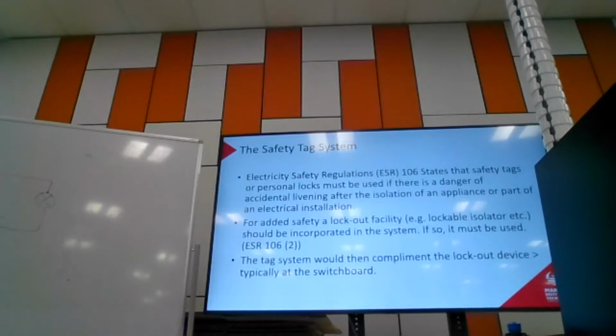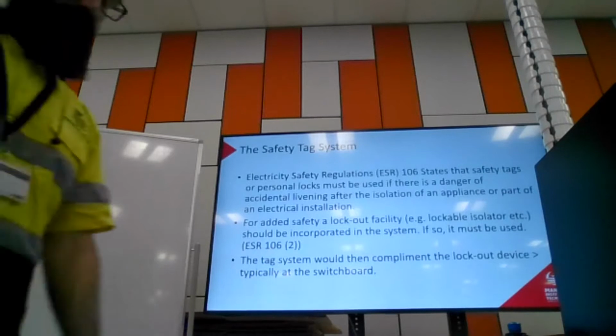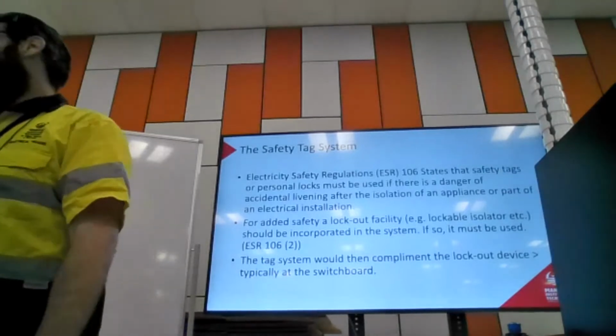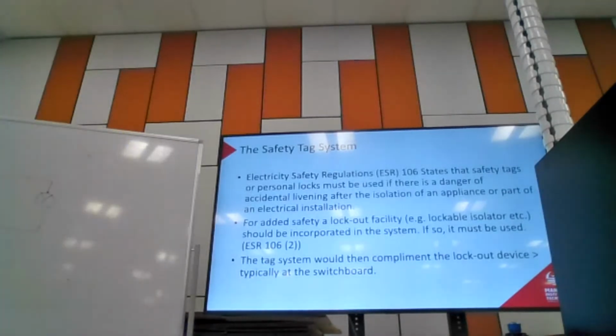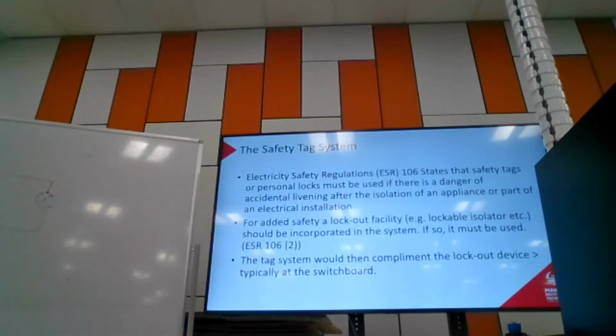So presumably then I could write something, right? I could just write one on a piece of paper and stick it on the switchboard. Do not switch this back on. It's dangerous. I'm working on it. Please don't kill me. And then it says that if works or installations have a locking facility for isolating them from the power supply, then any person isolating the works or installation must use that facility to lock the isolation. So if I can lock it, I must lock it. So if I read between the lines, then what does that also say?